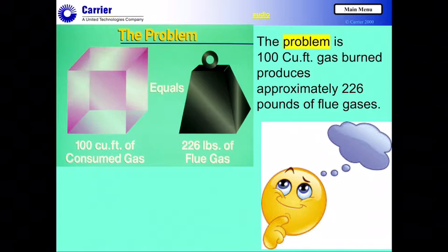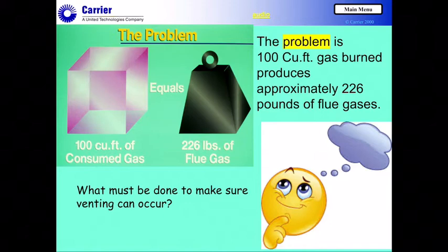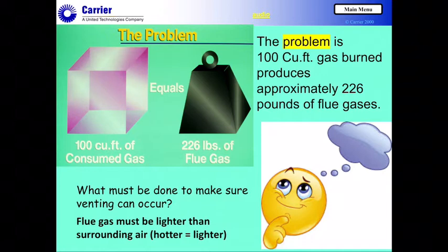Let's look at some problems associated with venting. If I consume 100 cubic feet of gas, that's not a lot of gas, but it would produce roughly 226 pounds of flue gases — that's an awful lot. So what do we need to do to make sure we can move 226 pounds of flue gases? The first thing that has to happen in any venting system is you've got to make the flue gases lighter than the surrounding air. The hotter they are, the lighter they are — it's really a matter of density.